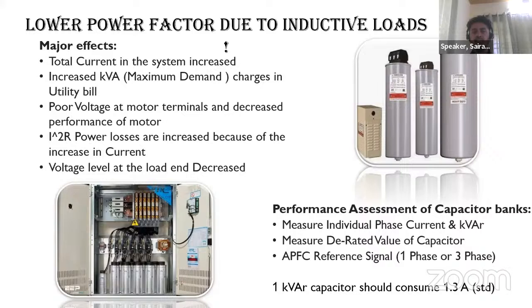Coming to the APFC, the way that we will be performing the performance assessment of capacitor banks is by measuring the individual phase current and kVAR. The individual phases are measured just to make sure that all three phases are working in a proper way. Then, by comparing this phase current and kVAR with the rated capacity of the capacitor banks, we can conclude the derated value of the capacitor.